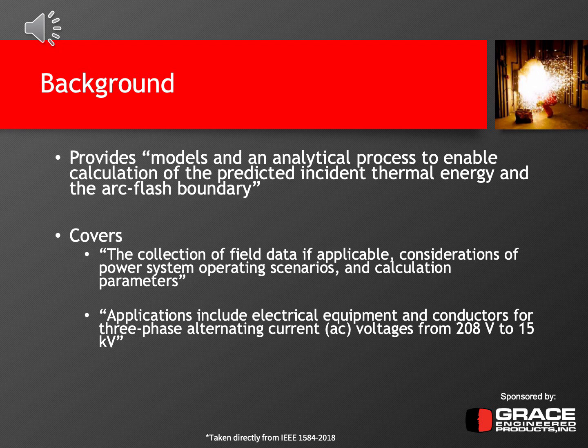It does cover the collection of field data if applicable. Whether the field data is collected by the engineer or whoever is running the study or not, it needs to be verified at some point. If not, then one of the main assumptions you should state is that field verification was not part of your arc flash study. So you assume that the drawings that were provided were true and accurate, and if they're not, then it might invalidate the incident energy analysis or the arc flash analysis.